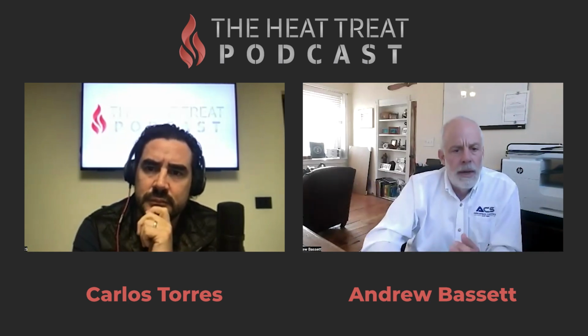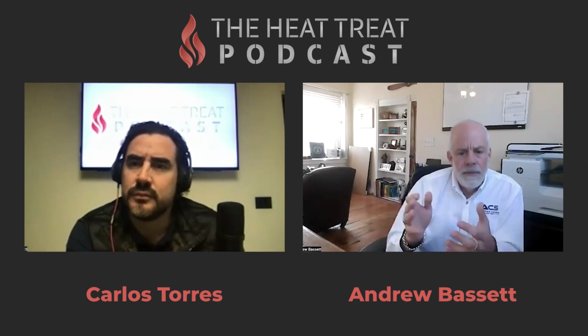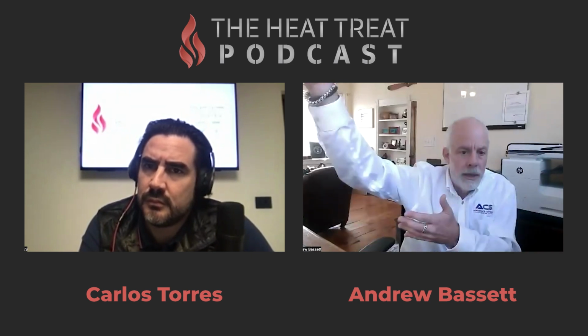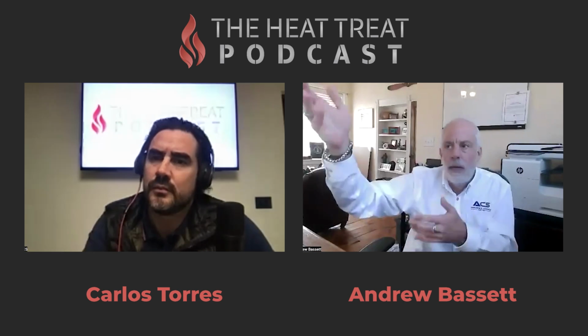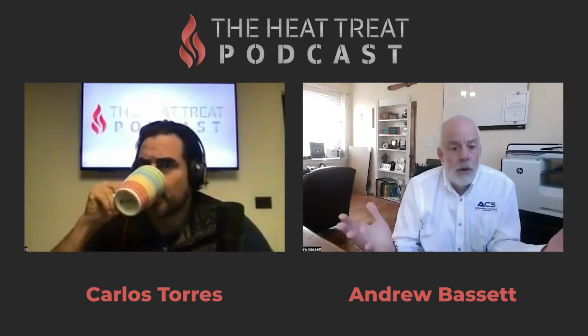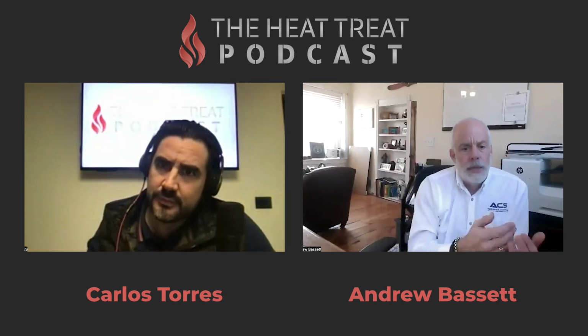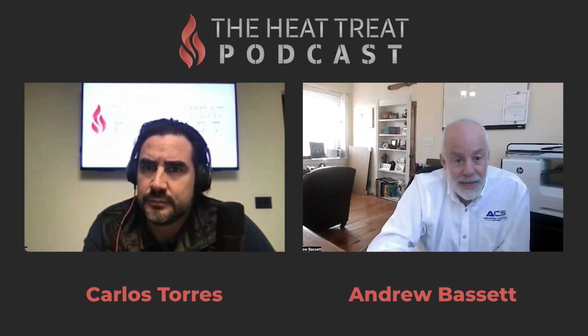No, a good pyrometry tech is going to start understanding the equipment over time as he's testing it. Hey, my results are starting to trend in this direction. Maybe we need to get maintenance involved, or maybe this person is maintenance. Oh, let's open the door. There's a big chunk of insulation or brickwork missing, and that's why it's cold in that area. And all this can be done through pyrometry testing. So the challenge, again, is finding good pyrometry guys. And if you do have a good pyrometry guy, you know what? You better pony up and pay them, because they're worth their weight in gold, in my opinion.